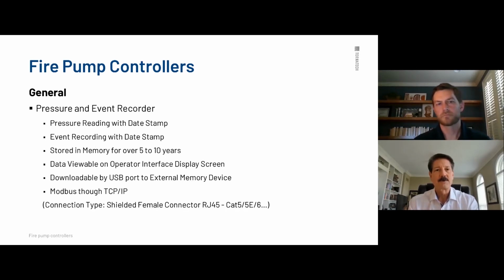We actually have quite a few event logging. We like to say almost lifetime as far as the number of events, but nothing's ever lifetime. Again, the requirement is storing it for 5 to 10 years for the events to be able to go back and review whenever necessary. Data viewable from the operator interface display screen really makes life easier. And we'll get into this down the road because we do have a color graphics touchscreen. That color graphics makes everyone's life easier, meeting these requirements by code of the voltage, the amperage, the condition of the motor, the pressure reading itself. And again, it's viewable from the front.